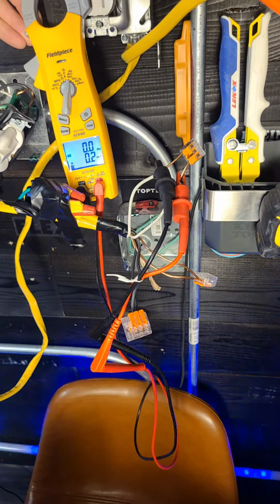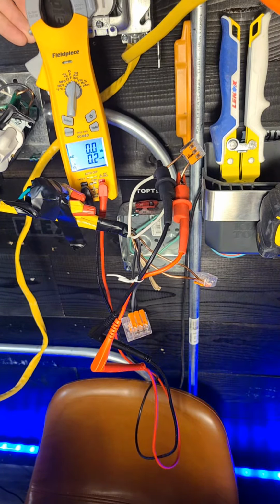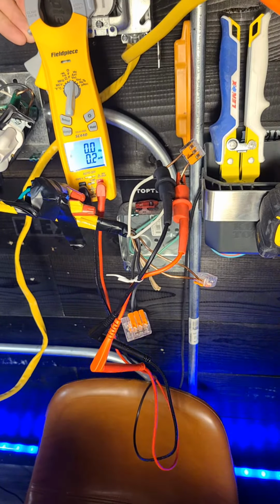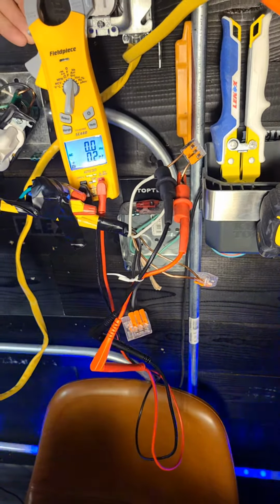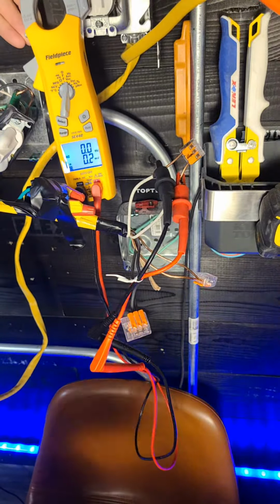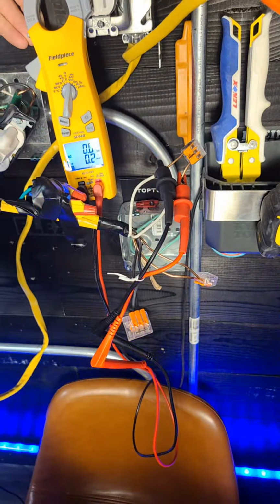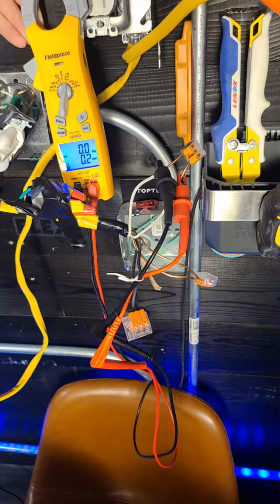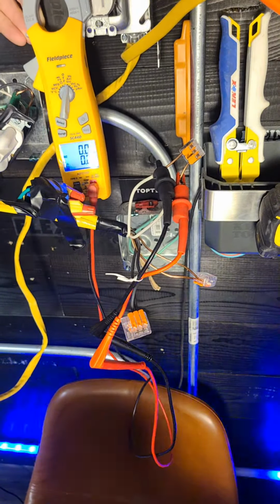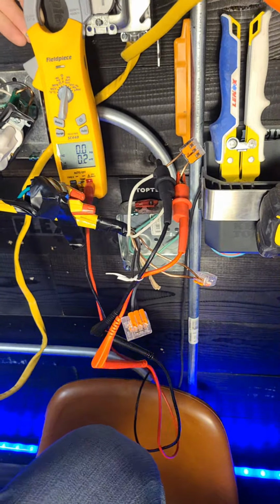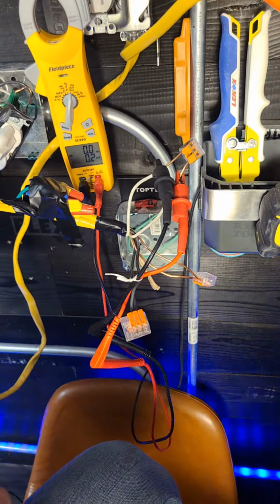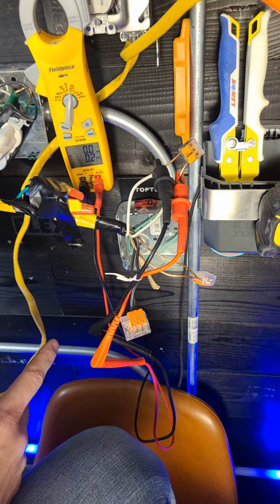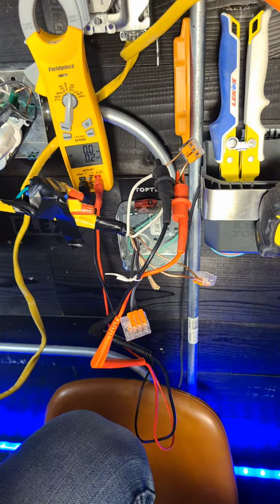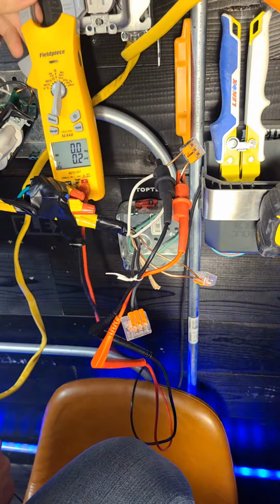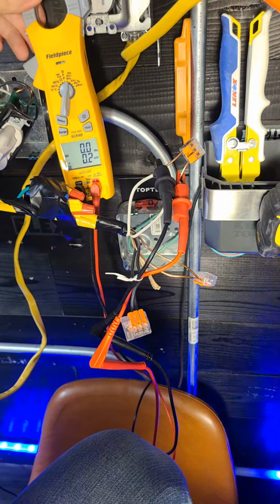So you can see where the amperage plays a factor on your voltage drop. Absolutely, but pretty solid connection here. 0.30 is usually a good sign of a problem. I've seen 100 on breakers at certain data centers I can't mention the name of. But I've seen 300 on Square D breakers in certain data centers I can't mention.